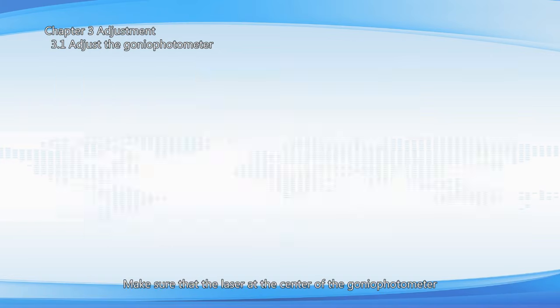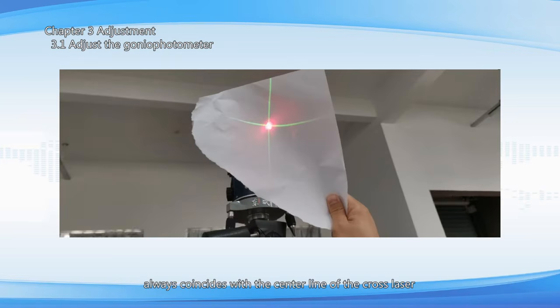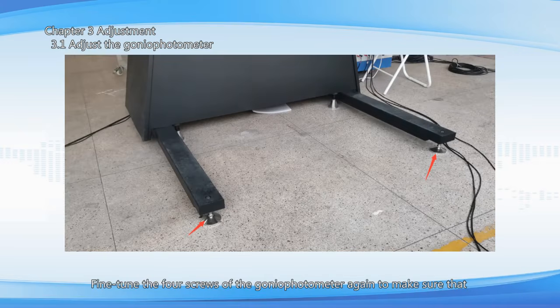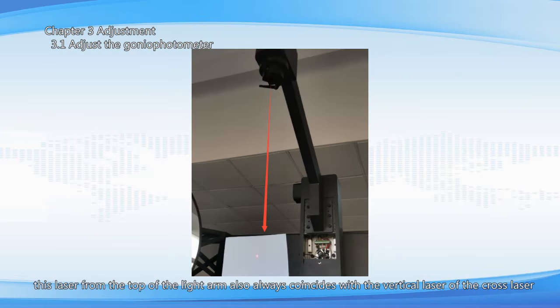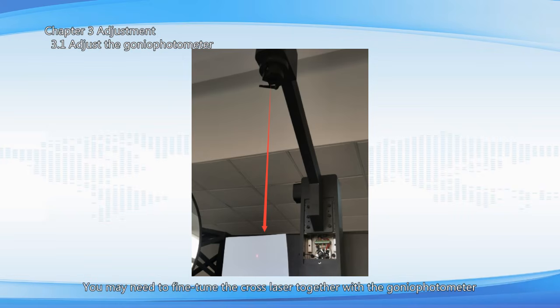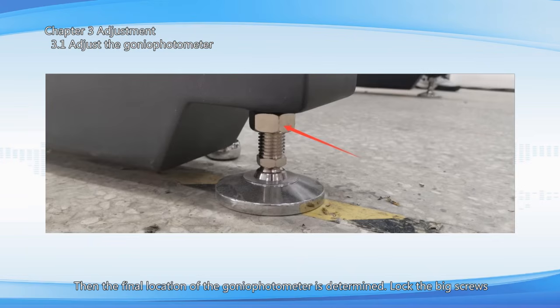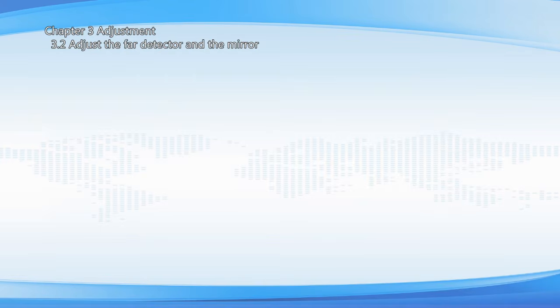Make sure that the laser at the center of the gonio-photometer always coincides with the center line of the cross laser. Fine-tune the 4 screws of the gonio-photometer again to make sure that this laser from the top of the light arm also always coincides with the vertical laser of the cross laser. You may need to fine-tune the cross laser together with the gonio-photometer. Then the final location of the gonio-photometer is determined. Lock the big screws. Adjust the FAR detector and the mirror.